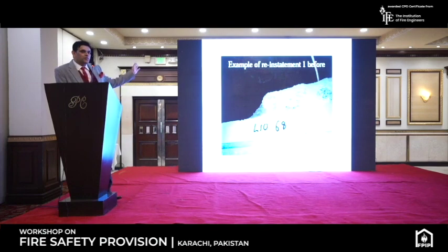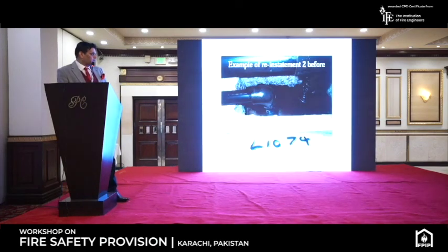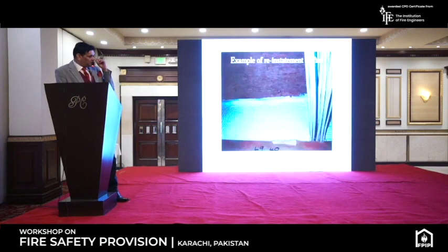Like in this kind of wall, we see this kind of opening. The solution is that there should be fire bags over there, which can close the opening. So in the case of fire, this area and the other area are both protected. These types of openings should be closed with fire barriers.